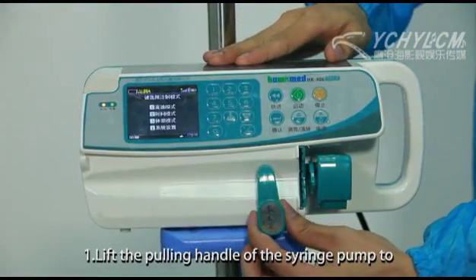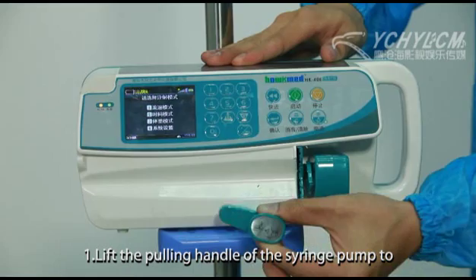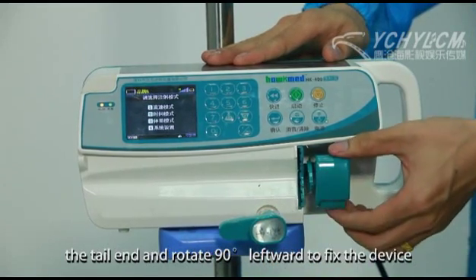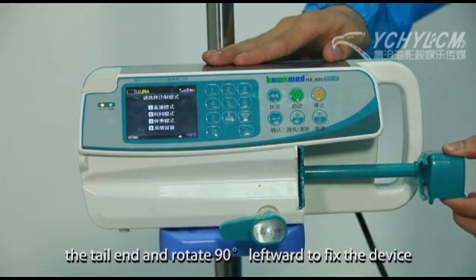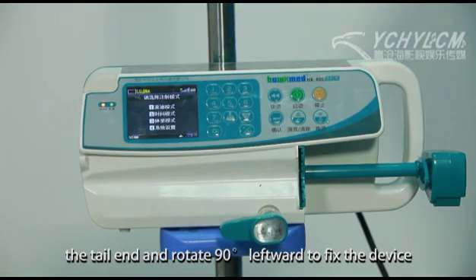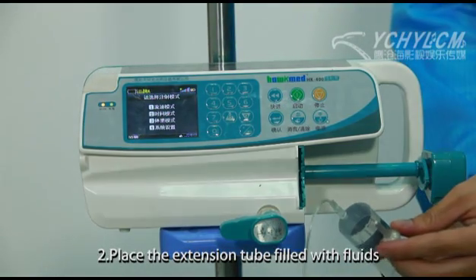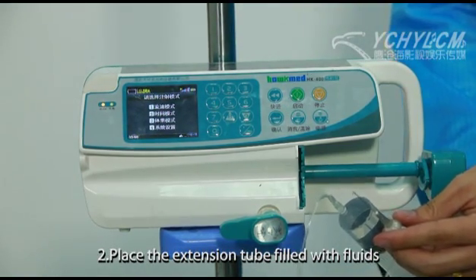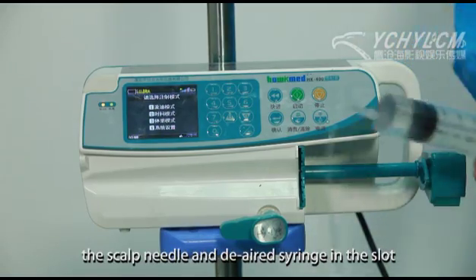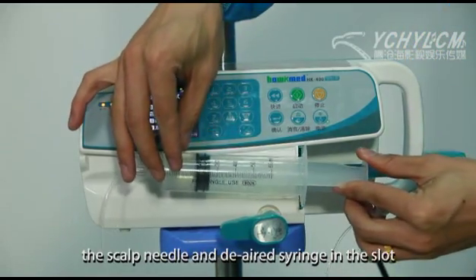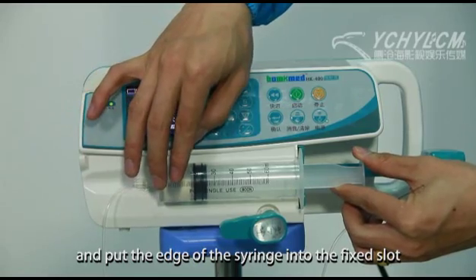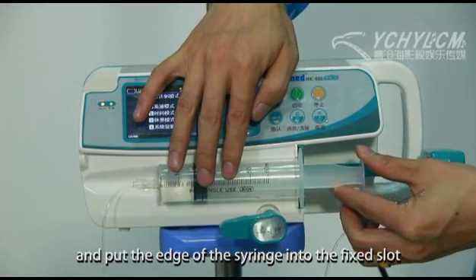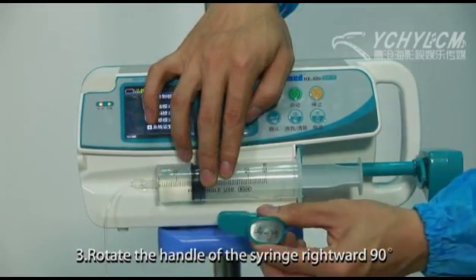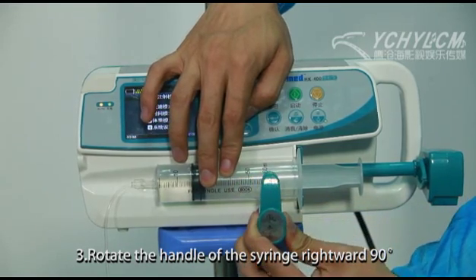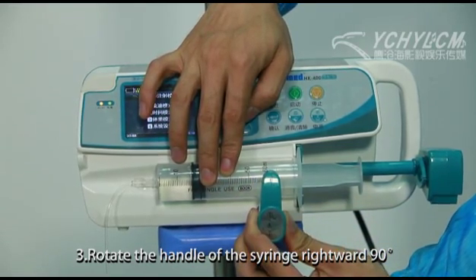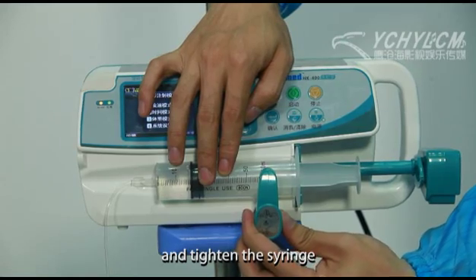1. Lift the pulling handle of the syringe pump to the tail end and rotate 90 degrees leftward to fix the device. 2. Place the extension tube filled with liquids, the scalp needle, and the de-aired syringe in the slot, and put the edge of the syringe into the fixed slot. 3. Rotate the handle of the syringe rightward 90 degrees and tighten the syringe.